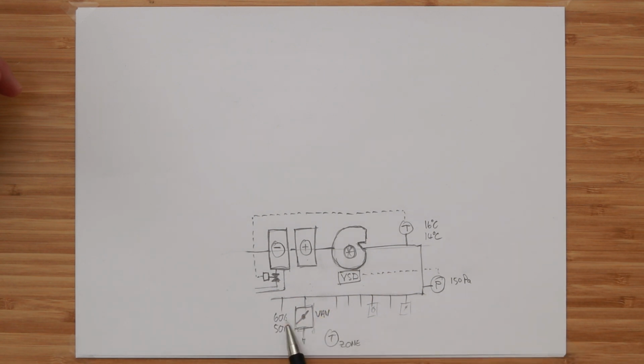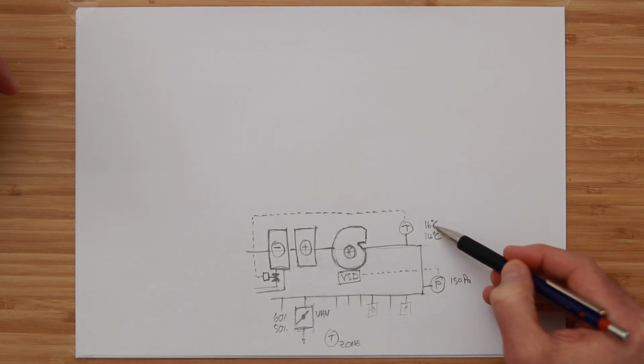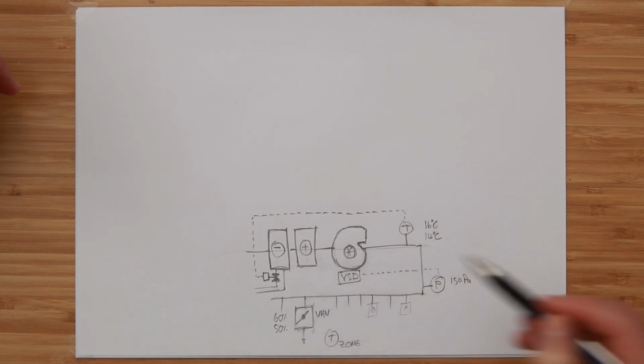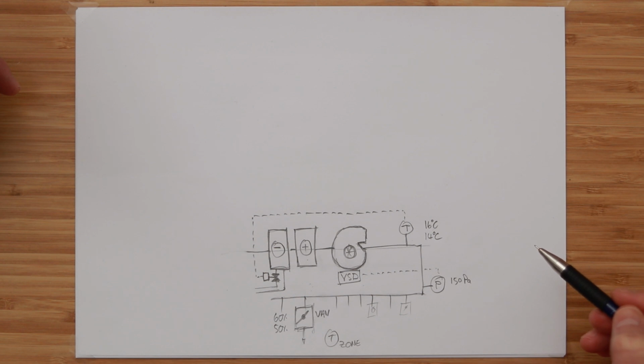So if that VAV damper was at 60%, or say all of them were about 60%, then that 2 degrees Celsius colder air would cause all these dampers to close off just a little bit, say 10%. And when that happens, the duct pressure goes up slightly and the supply fan slows down. So there is an indirect relationship between the supply air temperature and the speed of the fan. Most people don't realize that.